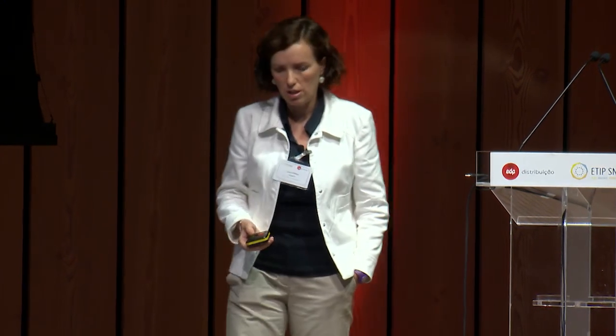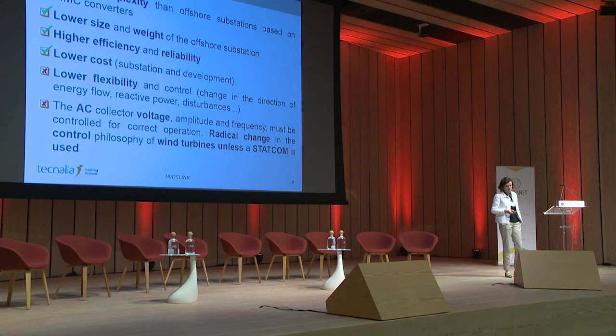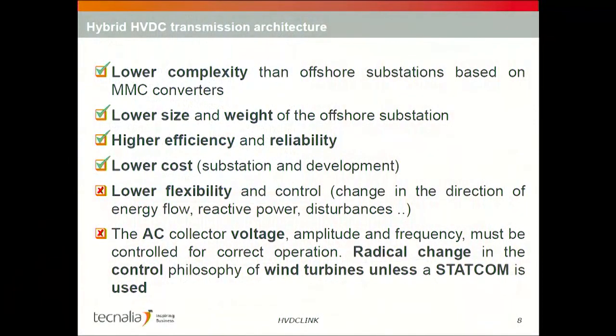The advantages of this solution with respect to the VSC MMC converter are that it has less complexity, lower size and weight, high efficiency and reliability, and lower cost. But on the other hand, it has lower flexibility, and we have to control the AC collector voltage. Depending on whether we use the STATCOM or not, as I said, it's optional, but if possible we have to control from the wind turbines instead of the substation converter, and it's a radical change.